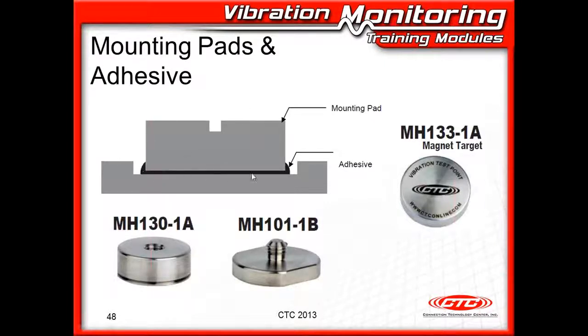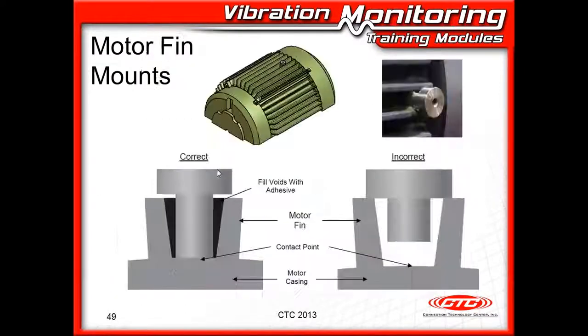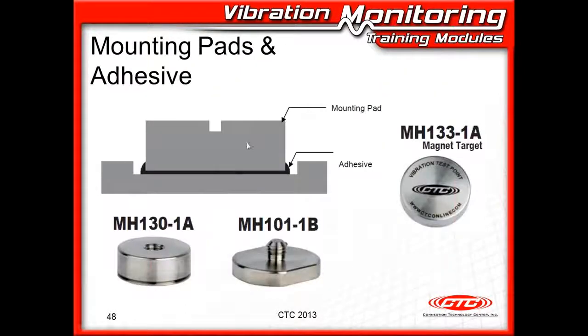Here are our adhesive pads. Again, we're going to need a flat surface, whether it's a spot face or if you're just taking a surface down with a grinder or a file, you still need to have that flat surface. And as I mentioned, it has to be clean, clean, clean. There's no substitute for cleanliness here. If you don't get it clean, this epoxy is not going to hold for you. So get everything cleaned up and dried up. Get your epoxy in here and set this in place and hold it in place either with some duct tape or a bungee cord or something like this until this epoxy can set up and dry.